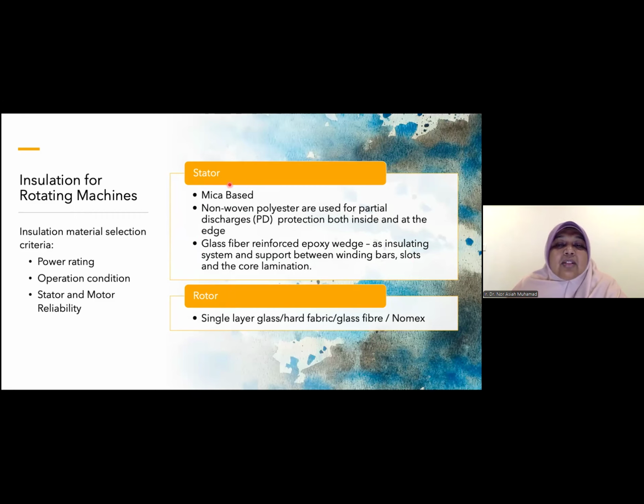For the stator, most of it is mica base, non-woven polyester used for partial discharge protection. They also use fiber, glass fiber reinforced epoxy resin. Then in the rotor, most of it is single layer glass or hard fabric, or Nomex. Maybe some of you are very familiar with Nomex. Now it's become famous. Yes. These insulating materials are selected based on the power rating of the machine and the operating condition. Like I said, we have hydro, we have gas, a few types of generation and operating conditions. Then the motor and stator reliability.